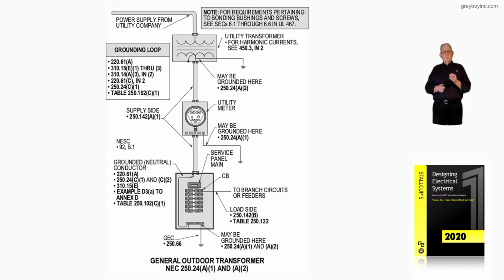220.61(A) deals with the neutral having to be sized to carry the unbalanced load. So I'm just giving an example. If we had 150 amps on L1, 120 on L2, and 130 on L3, then the neutral would have to carry 150 amps. That would be 220.61(A). 310.15(E)(1) through (E)(3) deals with how you use the neutral in the electrical system. Now (E)(3) of 310.15 is important.